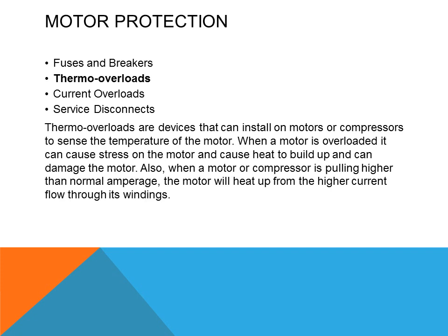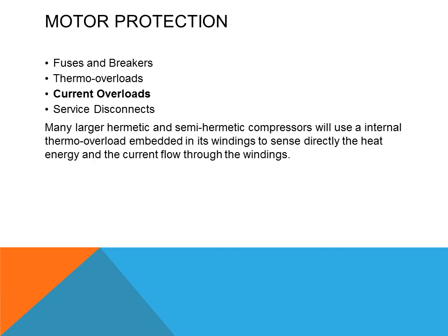Thermal overloads are devices that can be installed on motors or compressors to sense motor temperature. When a motor is overloaded, stress causes heat to build up and can damage the motor. Higher than normal amperage also causes the motor to heat up from increased current flow through its windings. Many larger hermetic and semi-hermetic compressors use an internal thermal overload embedded in the windings to sense heat directly, making it more sensitive than an external relay or overload.